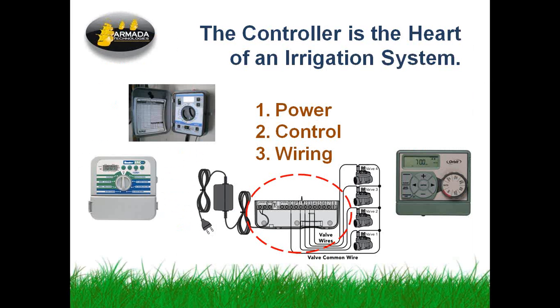The controller is the heart of an irrigation system. This is why we do this test here — because it stands between the power source and the remotely operated valves in the field, and applies power to them, opening them and releasing water to the zones based on the program we give it. Because it does all these things, we can find power, control functions, and wiring all in the same place, very conveniently located typically inside the face of the box.